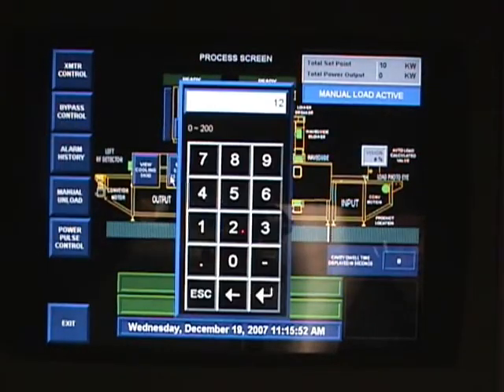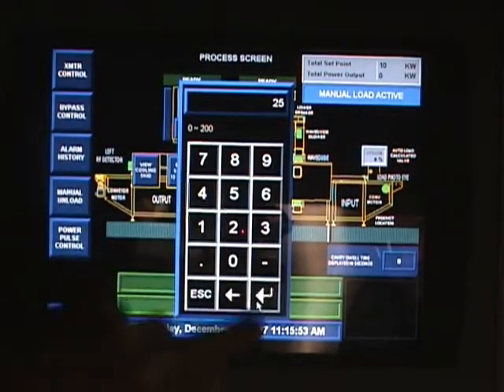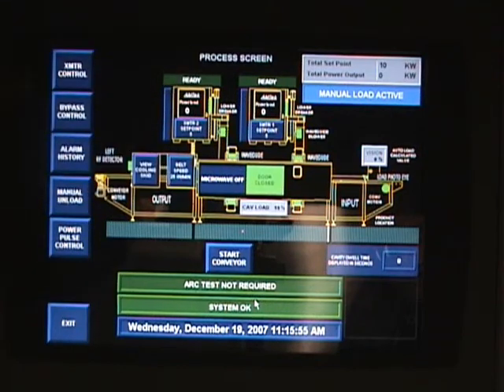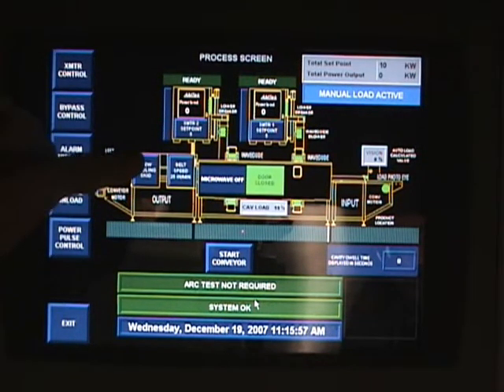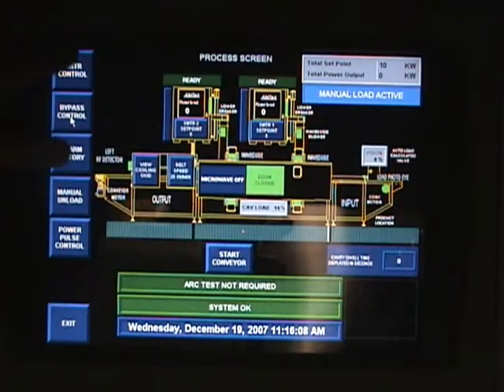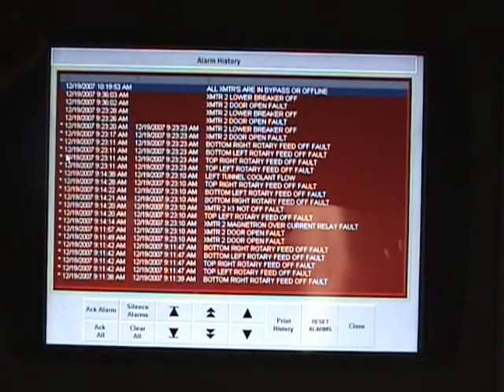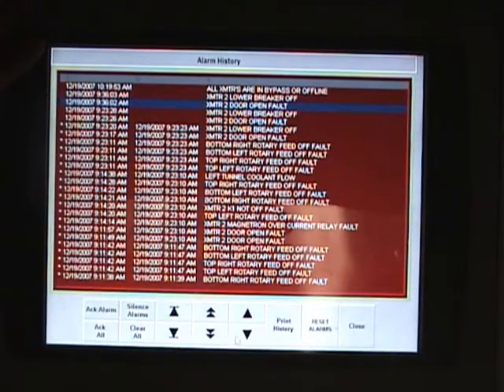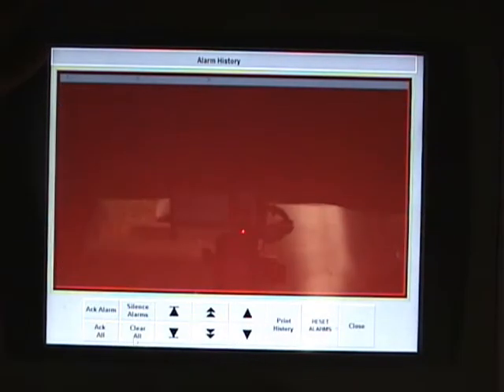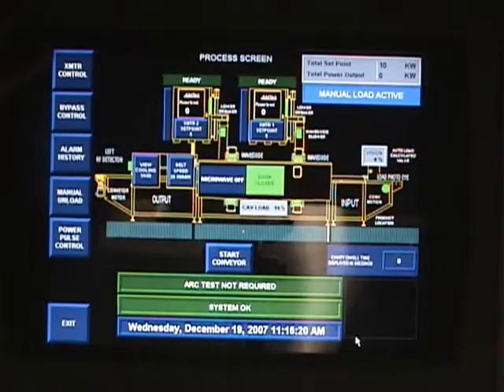Belt speed is digital — you can change the belt speed right there with that button. The cooling skid shows you all the I/O in the cooling skid that maintains the tunnel's temperature. You also have the alarm history screen, which shows all the alarms that happen, the time of day, and the dates. Those can be cleared at any point or printed out.